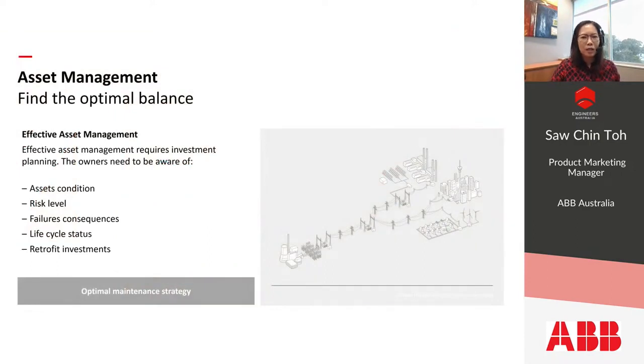In a plant, we usually face challenges in asset management. The user often has to look at ways to improve the availability and reliability of physical assets while thinking of ways to minimize the risk as well as the operating costs. There's a lot of pull and push factors here. The asset managers, the facility managers, or the maintenance managers often need to evaluate the situation based on the asset conditions.